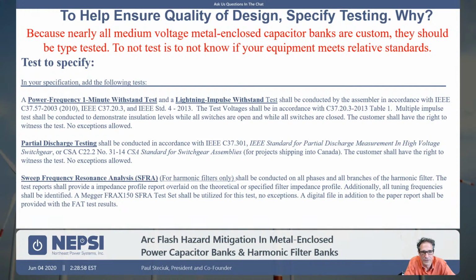So we have found that lightning impulse withstand tests and the 1-minute withstand tests are very important design verification methods to make sure that you actually get what you're asking for. It's critical to know that is being done. So I have included what I would suggest you put in your specification lines, that you have a power frequency withstand and lightning impulse. Partial discharge testing is another item that you really should be specifying, because partial discharge testing is a measure of the amount of corona that exists in the system during operation.